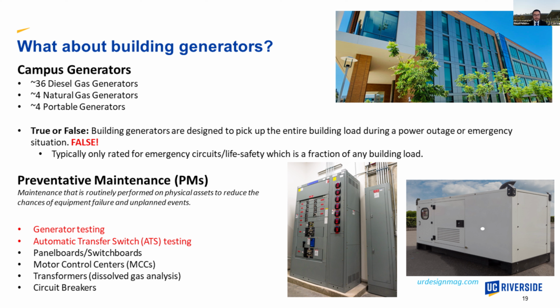True or false: building generators are designed to pick up the entire load during a power outage or emergency situation. This is false. It's typically only rated for emergency circuits or life safety type systems, which really is just a fraction of any building load.